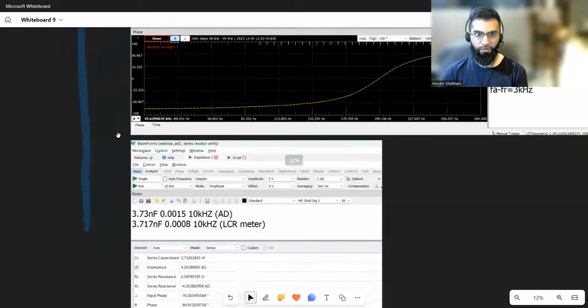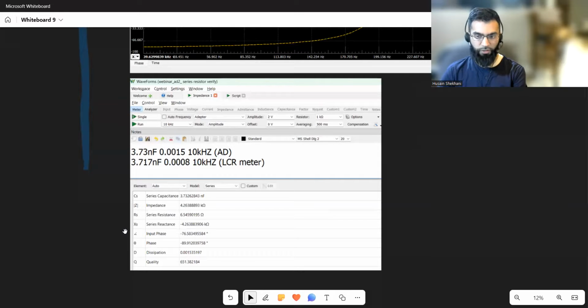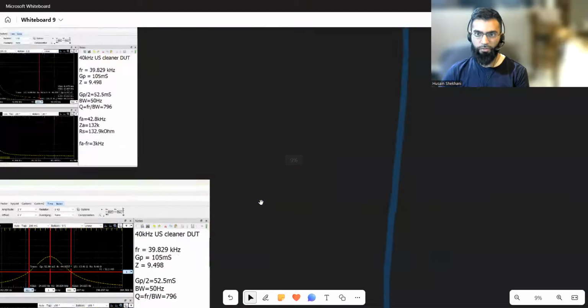The type of circuit being used is not the circuit to measure very accurate phase, but many times it's over good enough, or very good, for resonance, anti-resonance, impedances, or even capacitance in general, but not very accurate for phase. However, if you have a low Q, like a transducer such as a PZT5, or if you're measuring something that's already mounted in a device, this will still work. So you can still measure those phase angles pretty well.